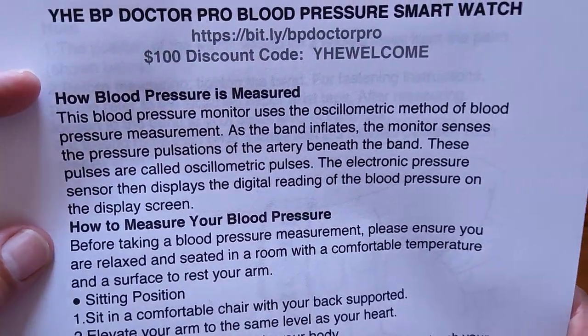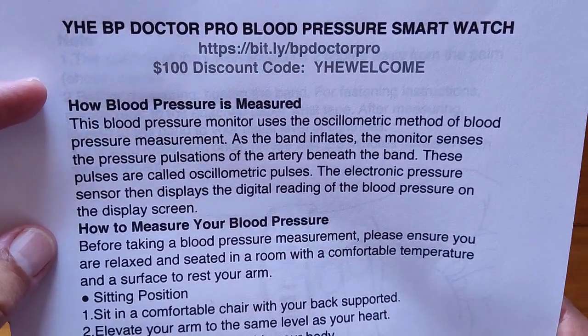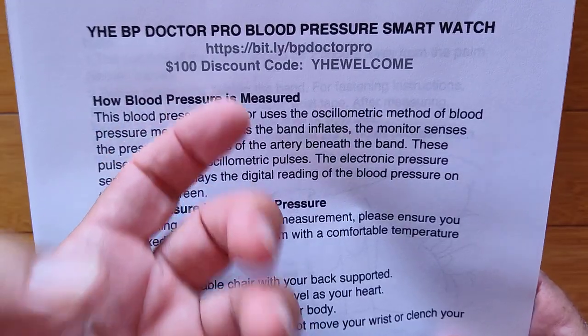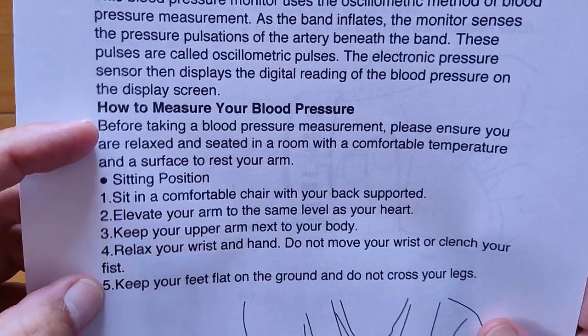How is it measured? It's a technique called oscillometric — that's how all the cuffs work. They pressurize your body, whether it's your wrist or upper arm, to the point where the device's microphone can't hear your heart beating. Then they let the pressure out; as the pressure releases they start to hear the first beat — the loud beat — then the second beat. That's your systolic and diastolic. This one does it on the inflation: it hears the pulse and when it stops hearing it, it knows it's gone too high, so you don't have to inflate all the way up and come back down. It's made a little bit speedier.